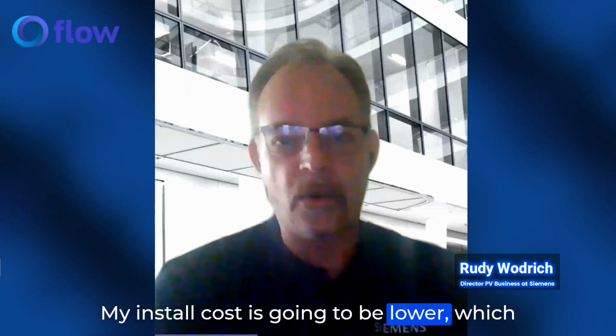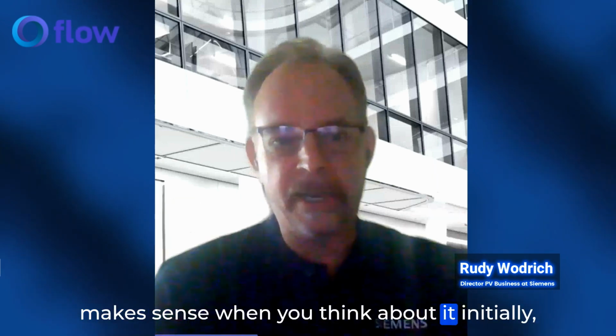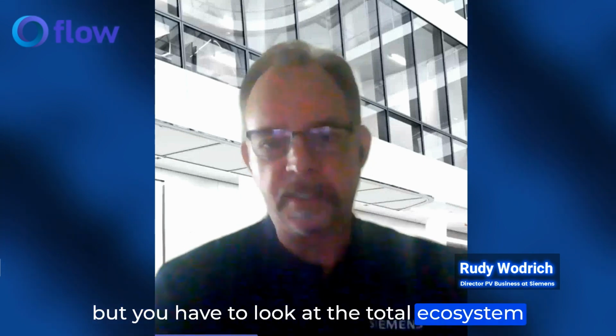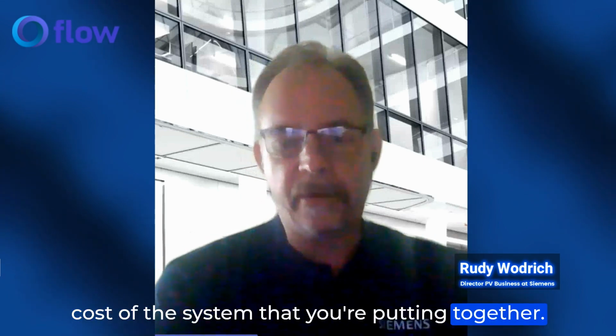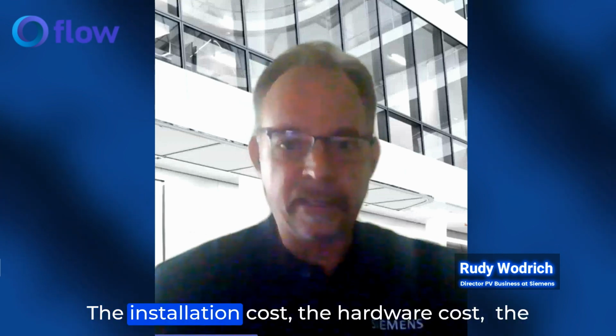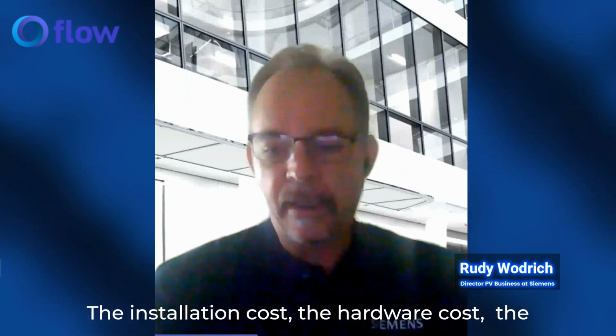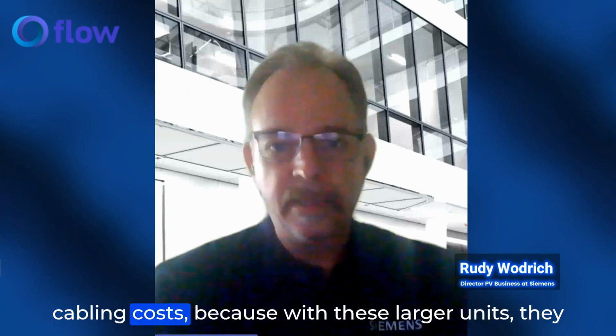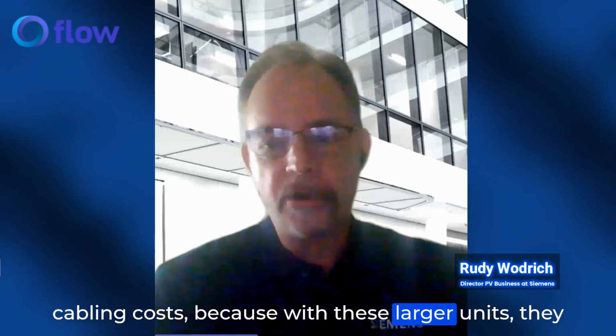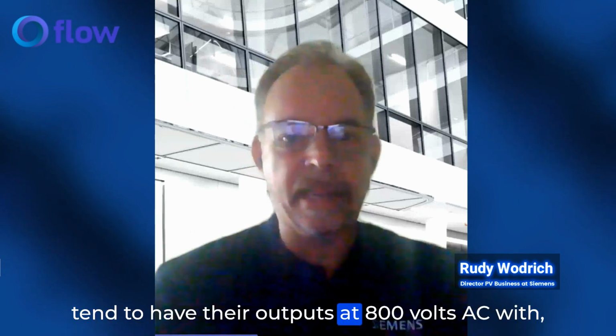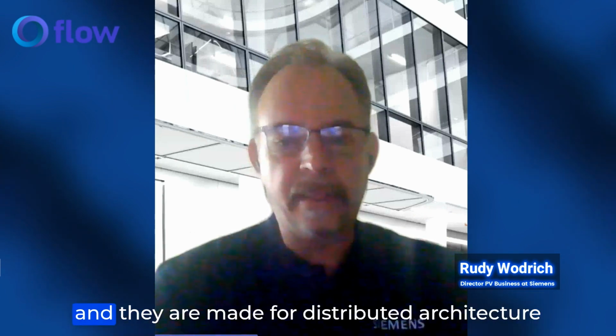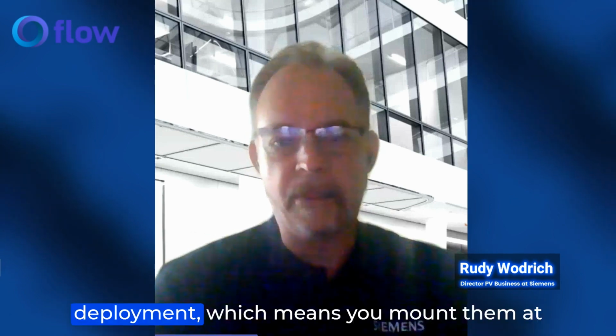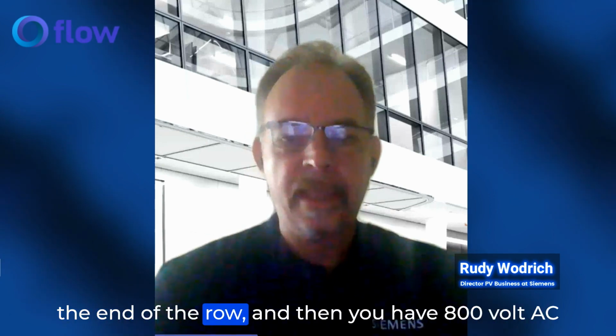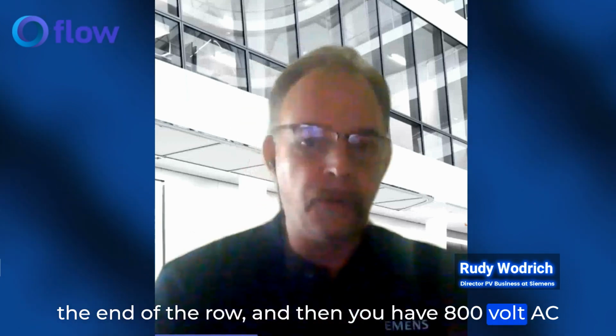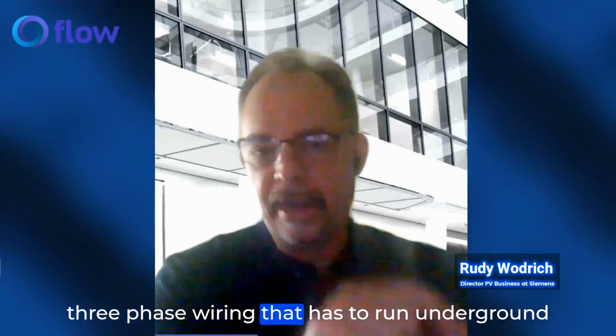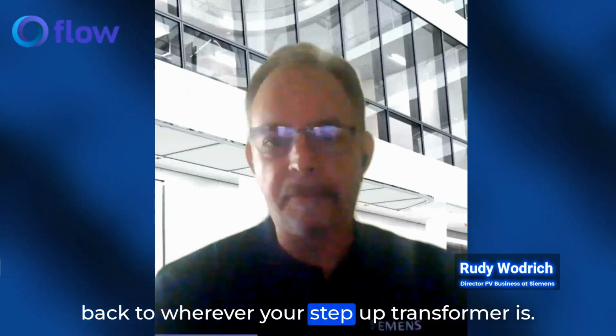My install cost is going to be lower, which makes sense when you think about it initially, but you have to look at the total ecosystem cost of the system that you're putting together, right? So that includes the installation cost, the hardware cost, the cabling costs, because with these larger units, they tend to have their outputs at 800 volts AC, and they are made for distributed architecture deployment, which means you mount them at the end of the row, and then you have 800 volt AC 3-phase wiring that has to run underground back to wherever your step-up transformer is.